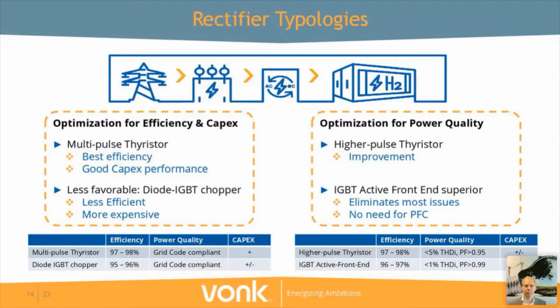If you want optimization for power quality, then a higher pulse thyristor solution, for instance at 24 or 36 pulses, offers an improvement in terms of power quality performance. However, if you are in an environment where there's severe harmonics in play and you have stringent measures to take into account, then an IGBT active front end offers superior power quality performance. This eliminates most of the issues altogether. And there's also no need for power factor compensation, which is the next subject that I will address.